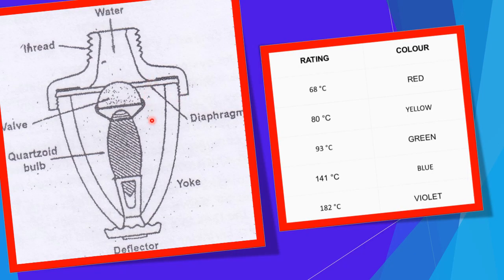Here you can see the same thing. If you look at the diagram, here the water is there, and this is the diaphragm, and this is the valve which holds the diaphragm in place, and these are the threads through which it is attached to the pipeline. You have the quartzoid bulb which holds the valve, and the valve holds the diaphragm, and this is the deflector plate shown over there, and this is the complete yoke. So for drawing purposes, you can utilize this diagram. Here you can see that red is 68, yellow is 80 degree centigrade, 93 green, 141 blue, and 182 violet. These are the color codings associated with it.